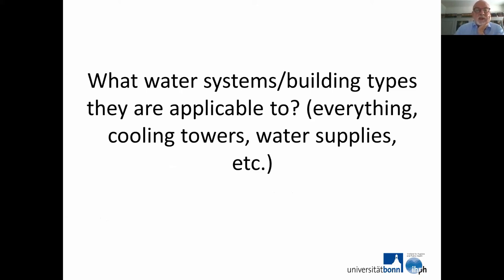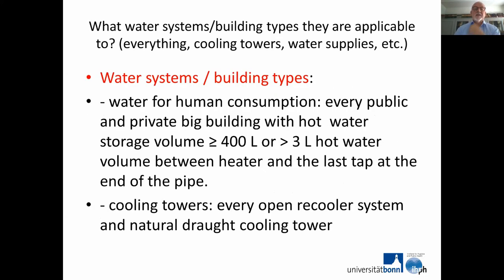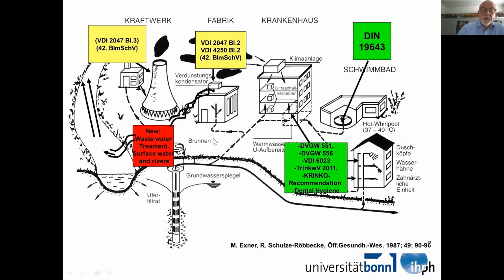What water systems and building types are applicable? Everything: cooling towers, water supplies, etc. For water systems in buildings, water for human consumption - every public and private big building must be monitored when they have hot water storage volume of 400 liters or more, or 3 liters or more of hot water volume between the heater and the last tap at the end of the pipe. They must be monitored. And the cooling towers - every open recooler system and natural draft cooling tower must also be monitored.